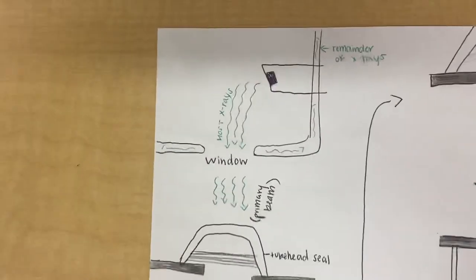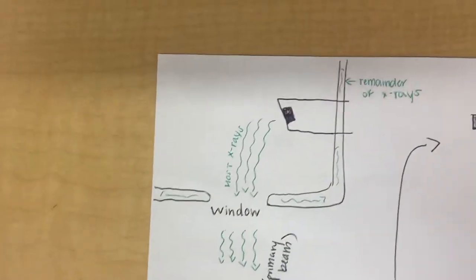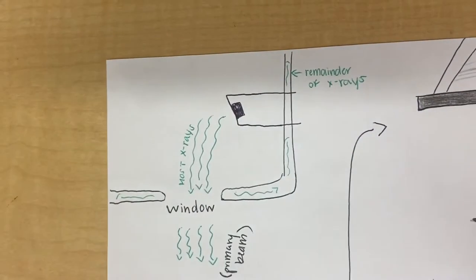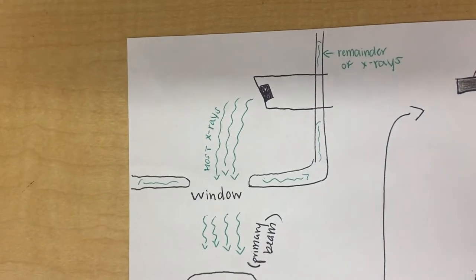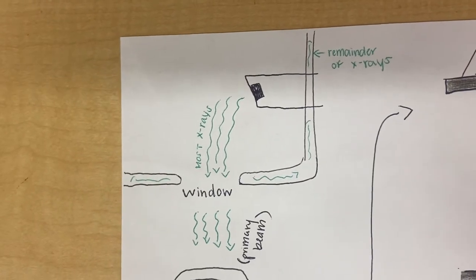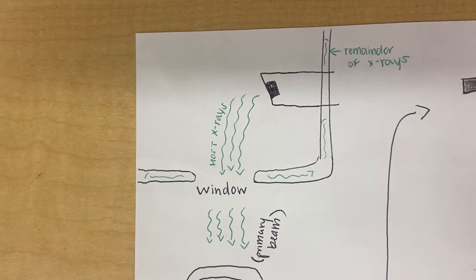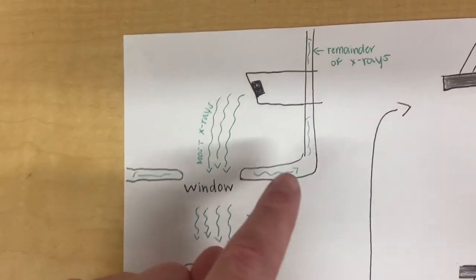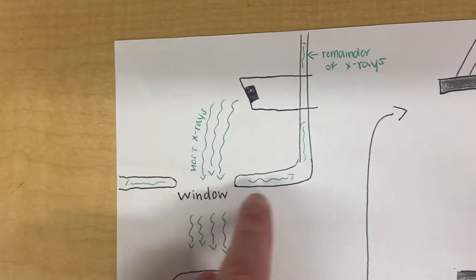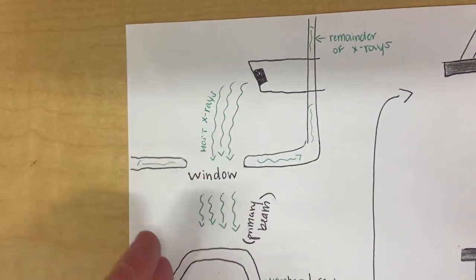The reason the tungsten target is at an angle, as you can see here, is so it can direct the X-rays towards the window and PID. The X-rays that aren't used will be absorbed by the lead glass housing surrounding the cathode and anode before it exits the window.